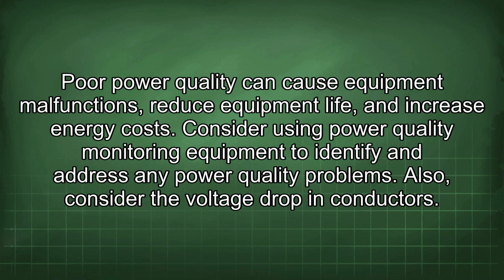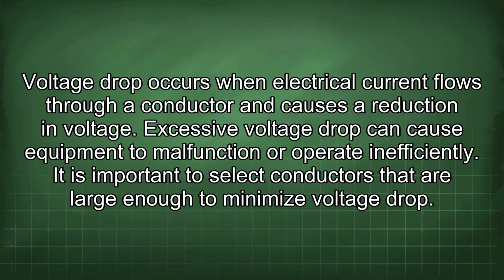Also, consider the voltage drop in conductors. Voltage drop occurs when electrical current flows through a conductor and causes a reduction in voltage. Excessive voltage drop can cause equipment to malfunction or operate inefficiently. It is important to select conductors that are large enough to minimize voltage drop.